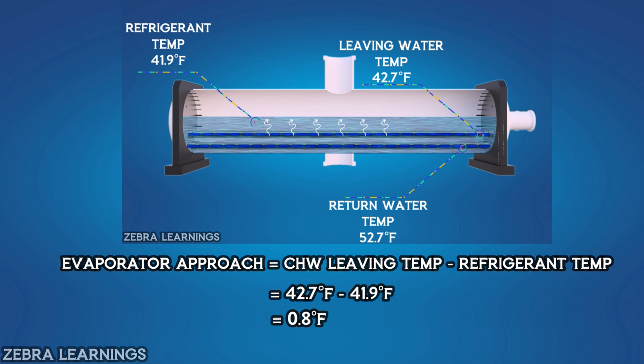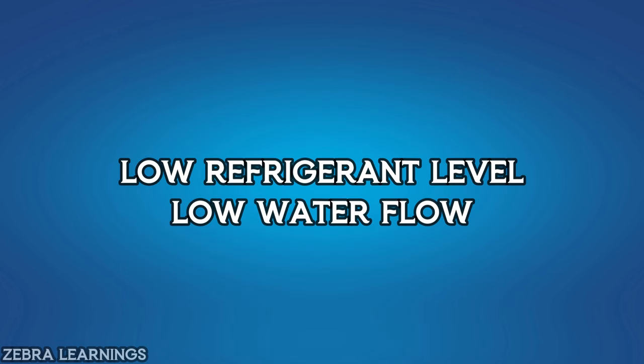An evaporator approach value below 3 degrees Fahrenheit indicates that heat transfer from the water to the refrigerant is happening well. If the approach value is higher than 3 degrees Fahrenheit, it means that heat transfer is not happening properly. This could indicate a problem with the coil such as scale formation. Additionally, a low refrigerant level or low water flow can also cause a high approach value.